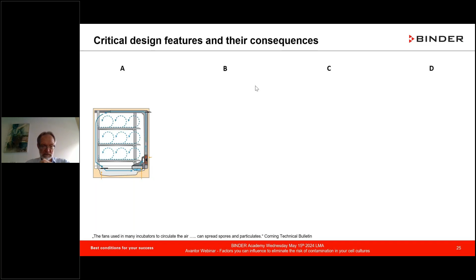Now here, you have shelf holders. You have air ducting systems, because there we have installed a ventilator which pushes the air upward. It is recycled throughout the CO2 incubator, is drawn back over the water pan, which is standard, into a HEPA filter, and then the cycle is closed and repeats itself. You have the HEPA filter right next to the shelves and your cultures, and you have a fixed water bath. Right? So those are the things where we would say, all right, not necessarily the ideal solution when you want to improve contamination management.